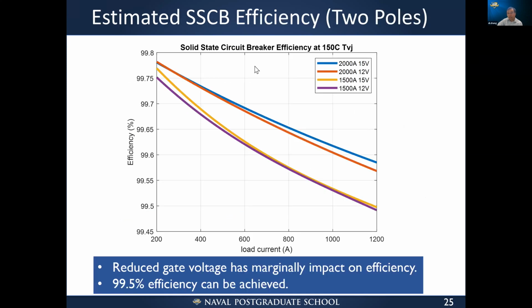So, estimated efficiency. This already considers two poles, so this is the total losses. Just two examples: one is 2000 amp devices, one is 1500 amp devices. As you can see, the 2000 amp devices are the latest generation of IGBTs, so they have lower losses and higher efficiency. These two are for the 2000 amps, and this is for the 1500 amp devices. These two curves show the efficiency difference when you apply 15 volts and 12 volts. There is some difference, but the difference is marginal.